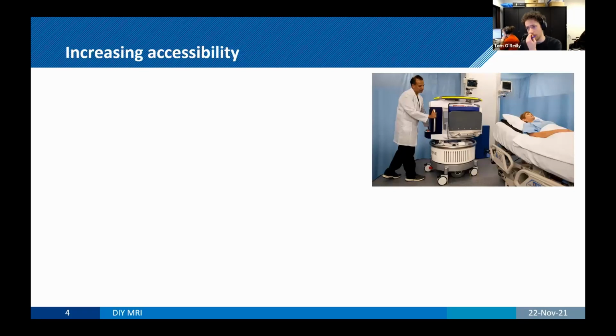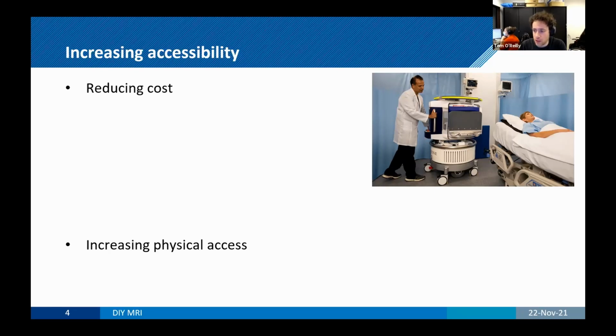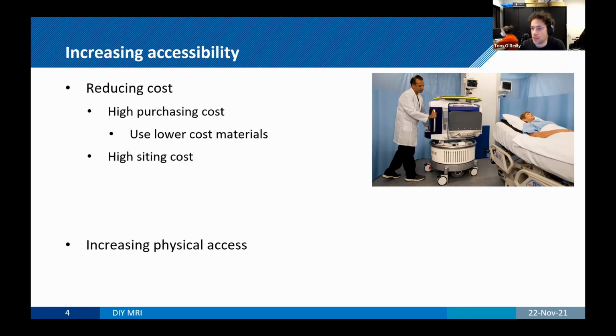So what can you do about it? How do we increase the accessibility to MRI? Well, obviously, you're going to have to reduce the cost of the system, but you also have to increase the physical access. These are two points that we feel in our group, where low field MRI can probably be quite useful. We're a little bit biased, obviously, because we like low field. To reduce the cost, you have to lower the high purchasing costs, which means you have to use lower cost materials, which typically will mean that your superconducting wires are out, because the wires themselves are very expensive, but also the cryostat is incredibly expensive.